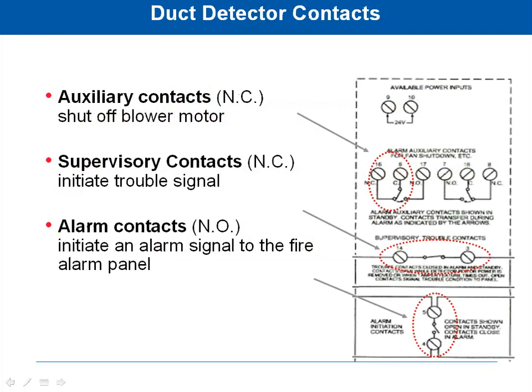Every duct smoke detector from every manufacturer has at least one set of contacts, typically called the auxiliary contacts, and he has one job in life. His job is to kill power to the fan motor. They're normally closed contacts, meaning that the power is being allowed through them. When the system alarms, because it senses smoke, those contacts open, which disables the power to the fan, shutting the fan down.